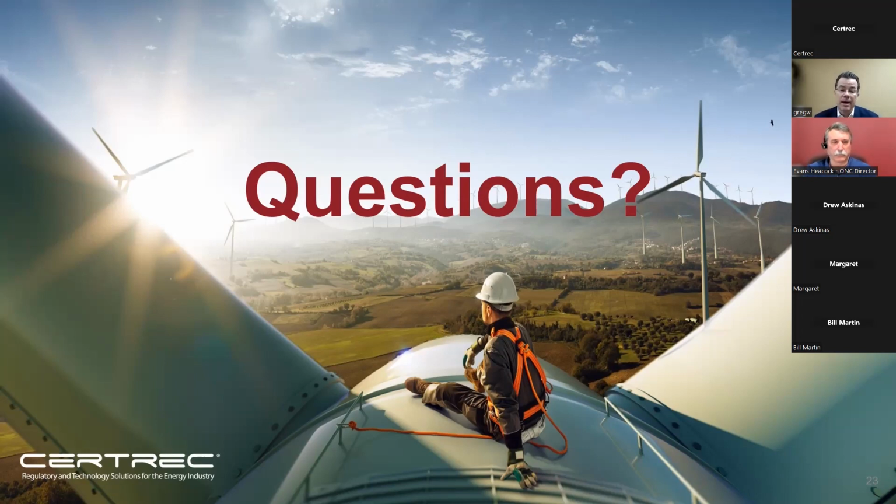Great question. I don't recall if they actually checked alignment, but I do recall once they repaired that arcing cable that we no longer saw that signature. And so I'd have to check the file and can definitely follow up as to whether or not alignment was an issue or not. But the pinched cable definitely was resolved.